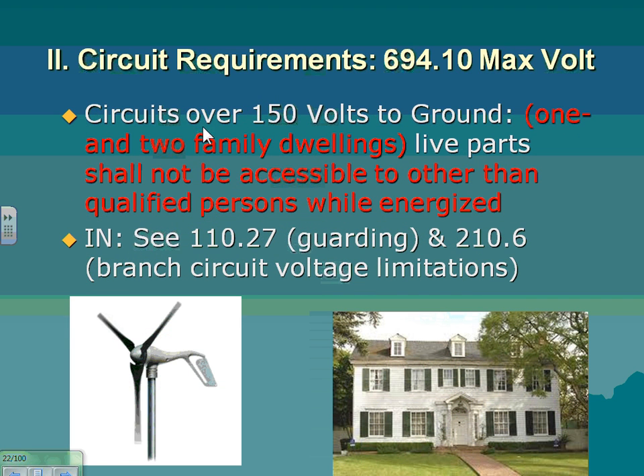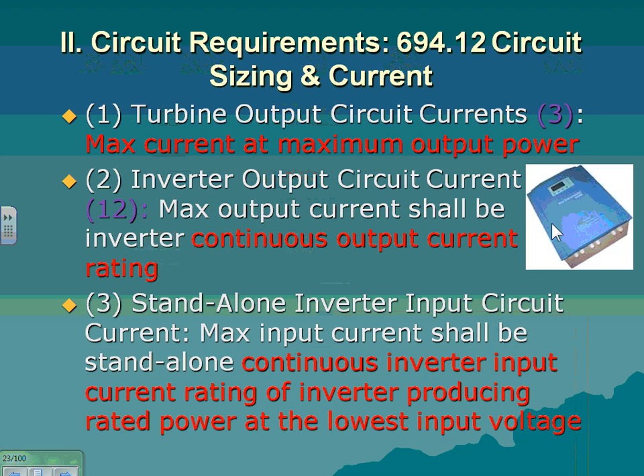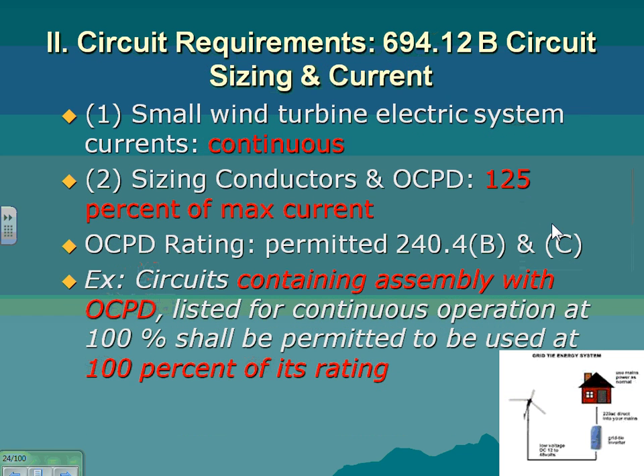Also in dwelling, if you're doing it on your farm, the voltage to the ground cannot be higher than 150 to ground. So that will limit you to a 208, 120 system, 240, 120. You can't put 480, 277 on dwelling, and shall not be accessible to other than qualified people. So there's limitation on the voltage that you can use here. Talk about the turbine sizing, and I'm running through because I want to take you to the solar. We don't have a whole lot of time, guys. I'm just showing you what the sizing and all this good stuff. I'm picking a couple of things.